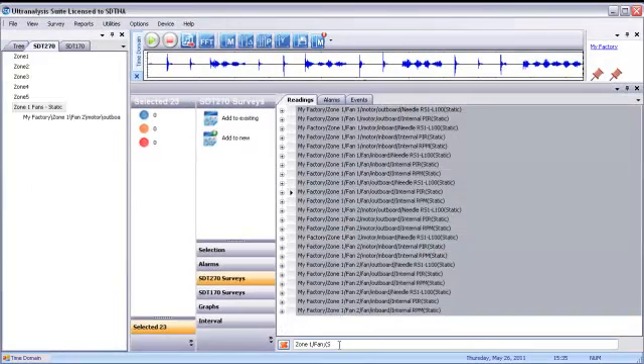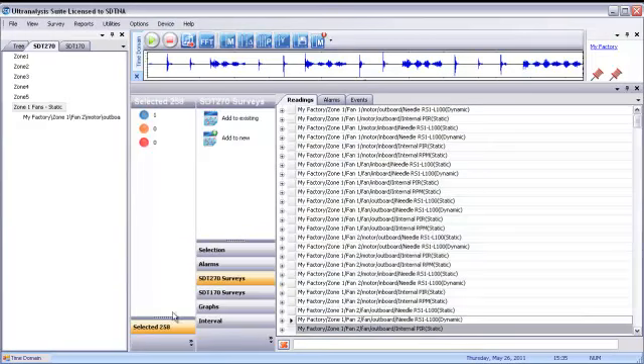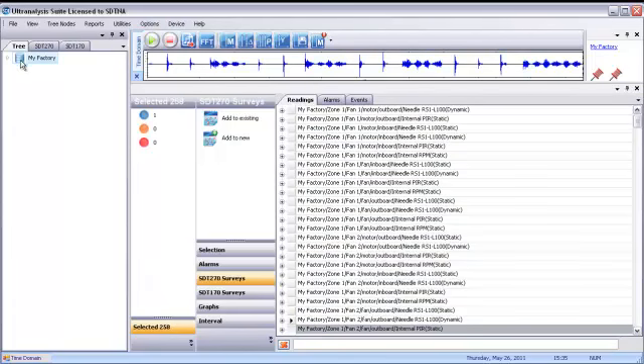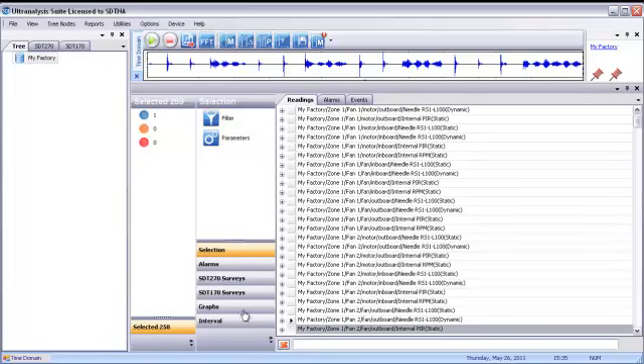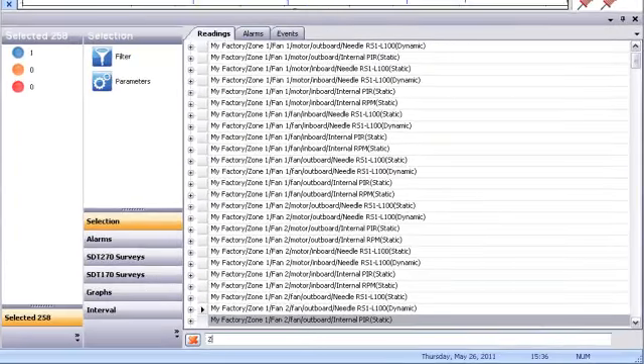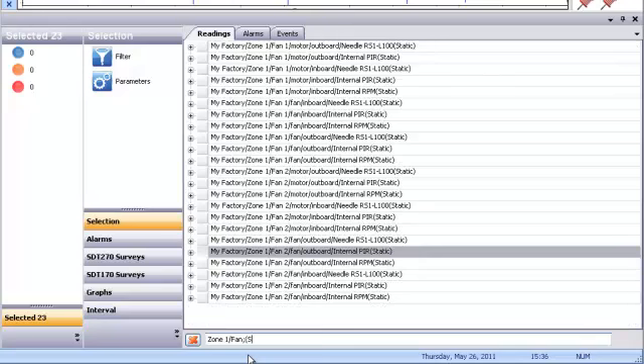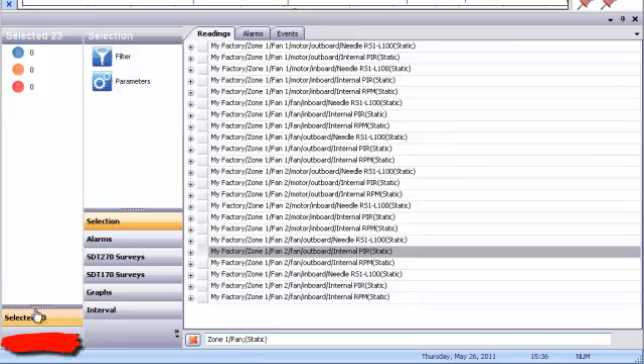Let's create a survey based on specific search criteria. In our existing tree, we have 258 measurements, but those measurements are a mixture of static and dynamic ultrasound measurements, as well as temperature and RPM. From our tree, let's extract a list that shows only our fans in zone 1. There. That narrows the list from 258 to 23. Now let's further refine our list by removing the dynamic measurements since we'll only collect data if our static data alarms.